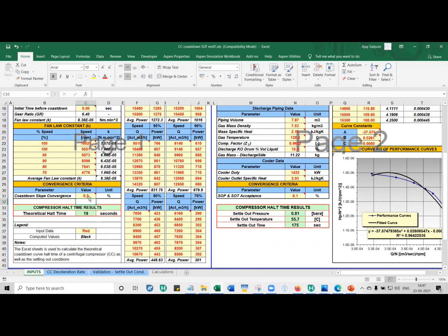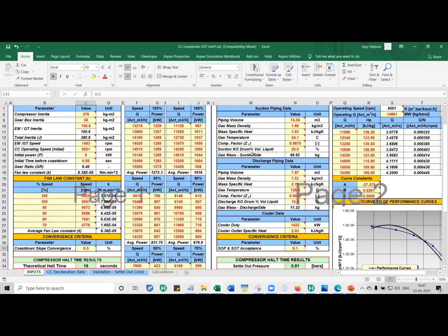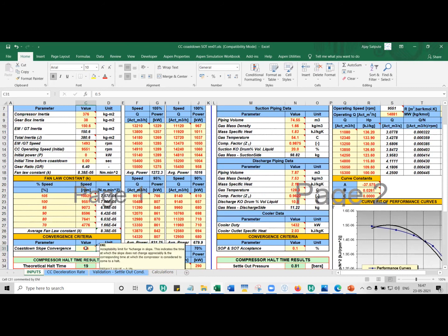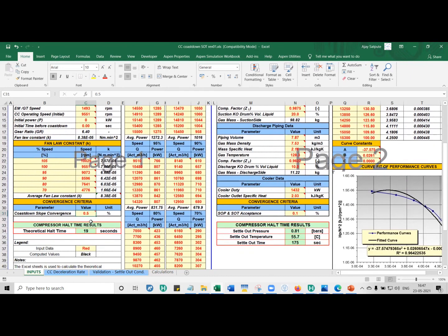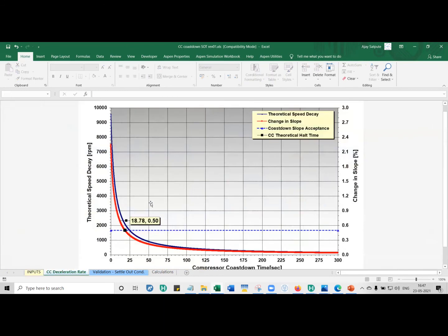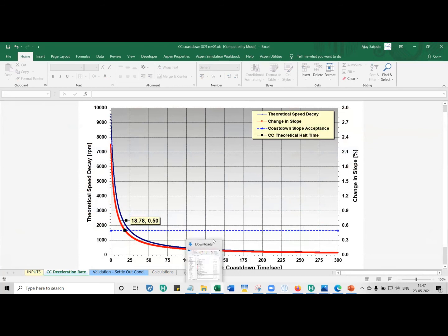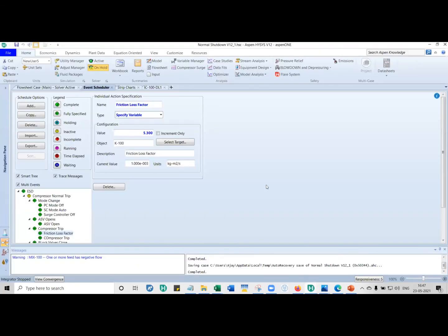So these numbers are conservative. But you can use it in case you are doing, either you ask the manufacturer or you have some field data. If you have some field data, you can play around with this convergence criteria itself to tell how long does it take for the speed to come down. And based on that, the idea is to impose this speed, this drop in speed into Aspen HYSYS. What we can do is we can use a friction loss factor. Using the friction loss factor, now this is trial and error. In my case I started with 1, 1.5, 2, 2.5 until I came to 5. Then I kept playing around.